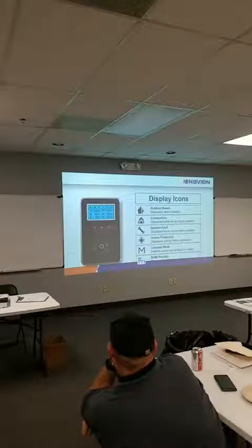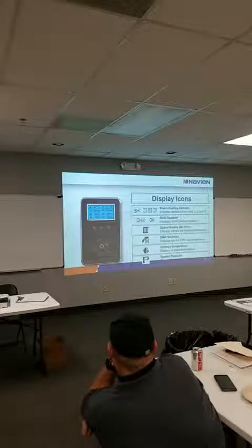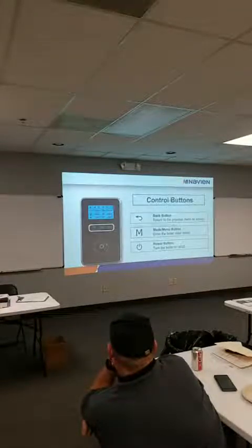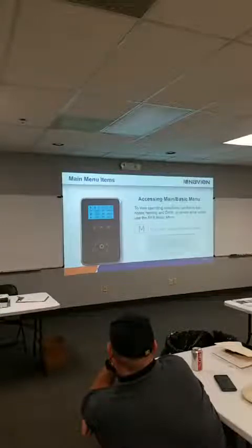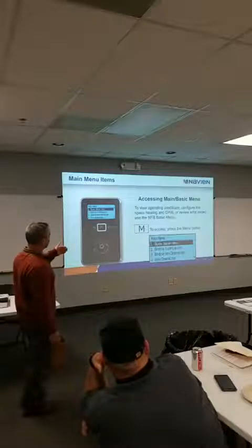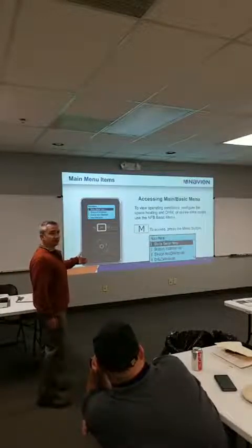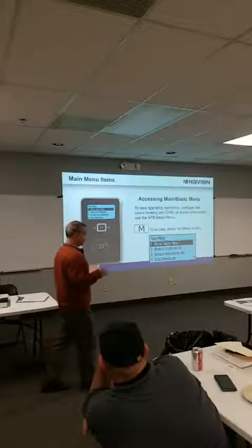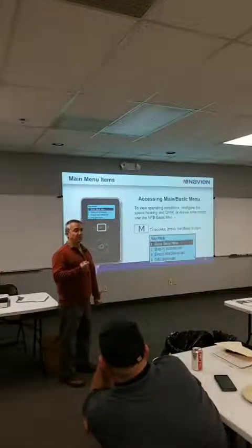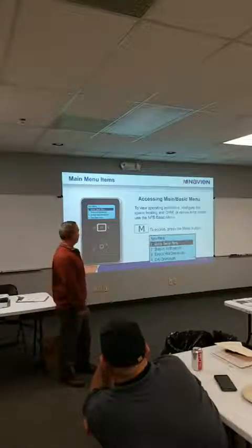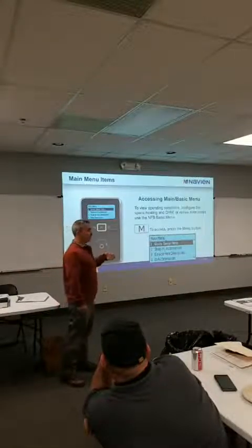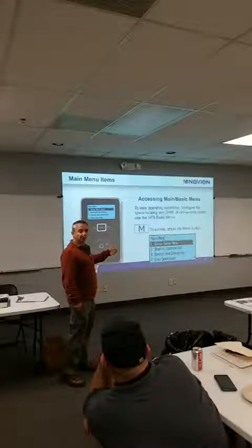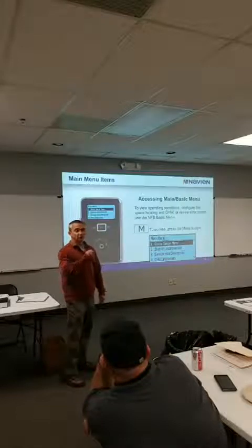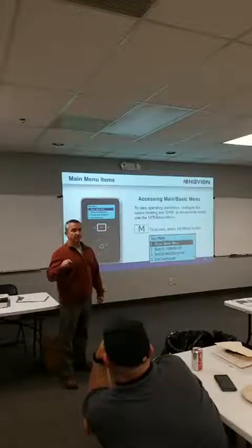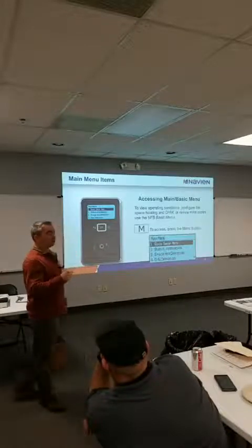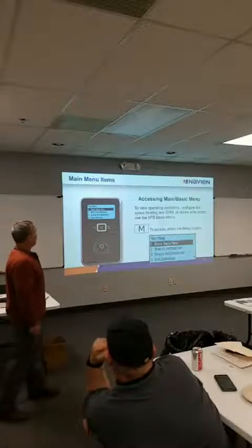What each of the settings mean, all your icons. I just went through all this: what the buttons do, what the dial does. When you hit the menu button, it puts you into the main menu. These are your setup options. All the updated equipment is going to have a quick start menu when you turn it on the first time, and I'll show you a picture of it. When we do the upgrade to this unit in a couple of months, it's going to have that new control in it, and it's going to force you to go through and set all the basic boiler settings up front. So you can either run it off the default that pops up, or you can make an adjustment right on your quick start menu. But then you can always go back in.